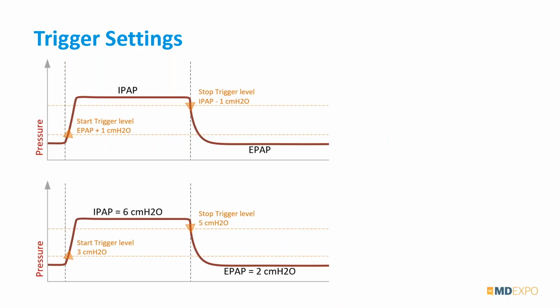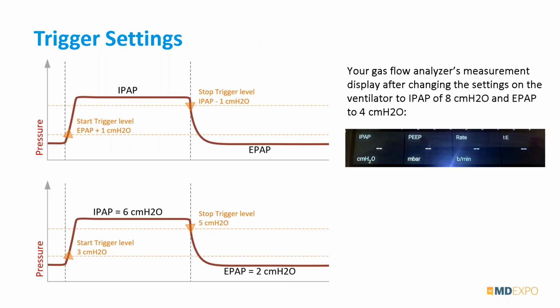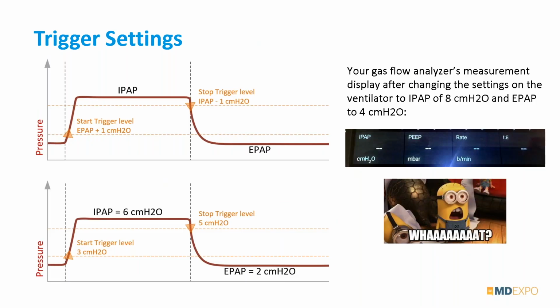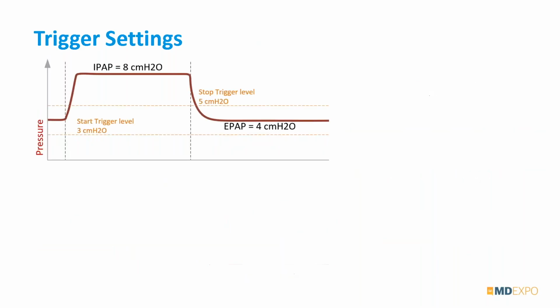But then let's say the next settings that you need to test is an IPAP of 8 and an EPAP of 4. And as soon as you change these settings on your ventilator, your gas flow analyzer is going to go, whoop, no measurements. Why is that? Because now we moved up the whole pressure levels to a higher level, right? And now, indicated by these dotted lines, our old trigger settings are no longer going to work, because my lower pressure level where I have my trigger settings, that's 3, is never going to be reached again. So that's why the analyzer cannot trigger anymore.